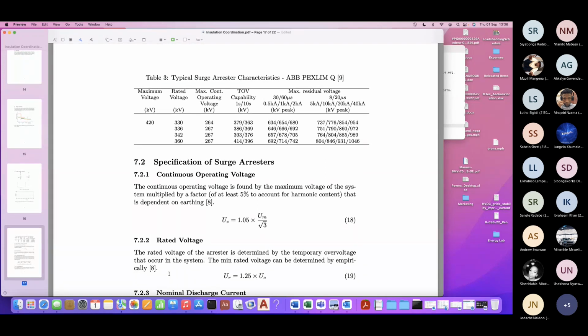Right, so typical surge arrestor characteristics. Let's point out a couple of things before we go any further. Maximum voltage 420 kV. Rated voltage 330 to 360 kV. How does that work? Maximum continuous operating voltage is less than the maximum voltage. That doesn't make sense, does it? It does make sense, because Um is a three-phase voltage, whereas your rated voltage and your maximum continuous operating voltage are phase to earth, or line to earth voltages. So you need to divide your maximum voltage, or your nominal voltage, by √3 to find your continuous operating voltage.